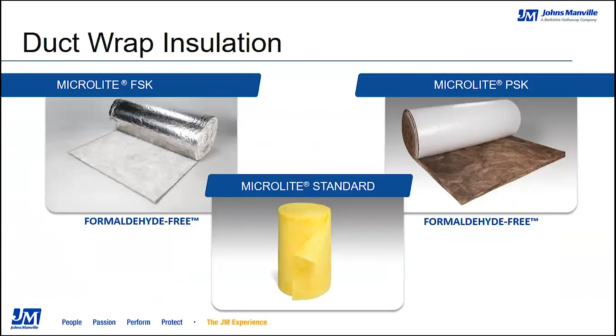Starting with Microlite FSK on the left: duct wrap comes in rolled form, typically 48 inches wide, with a pre-applied vapor barrier. It comes in 3 densities, which we refer to as type 75 (3/4 pound), type 100 (1 pound), or type 150 (1.5 pounds) — pounds per cubic foot of fiberglass in the product.